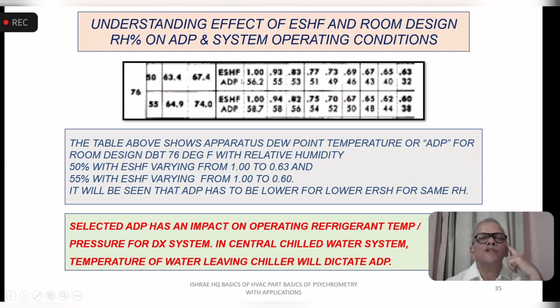If you have an effective sensible heat factor of 1, you will be selecting 56.2. But if it was 0.69, you will have to operate at 46. Imagine a situation where you have a chilled water temperature of 44 and you are expecting an ADP of 46. How taxing the coil selection will be.